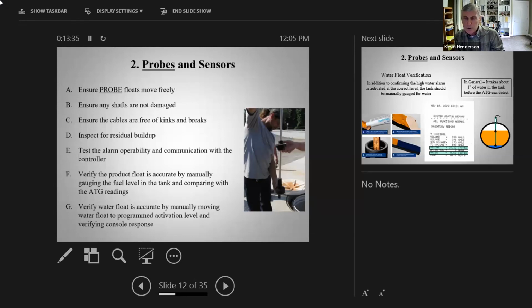And so the way that you do that, we had a question about that again, is once you pull the probe out of the tank, you'll get the probe out alarm. Lay the probe down on the ground, connect the wire back up, get it connected again, and what we'll do then is manually move the fuel float up the shaft a certain distance, and take a gauging stick or a tape measure, lay it down beside the ATG probe, and we will literally measure how many inches that float is up the shaft. And then we'll go back in and look at the console and verify that the console says, yeah, I've got very close to the same inch reading on my console as what I'm measuring out on the concrete pad with my stick or my tape measure. That's really the main thing we're trying to do there.